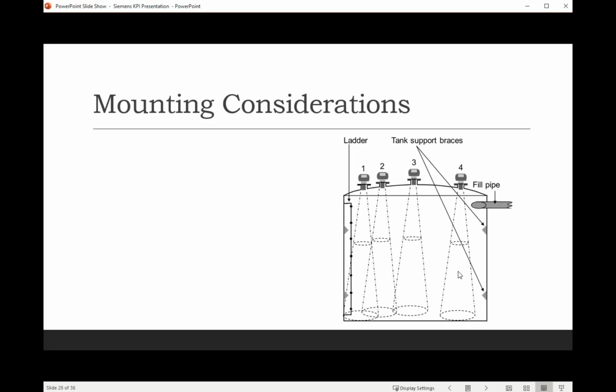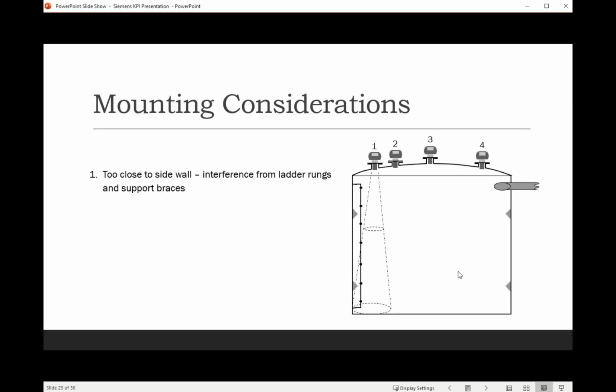So just for the transducer purposes, on this tank we have 4 different locations, and then in this tank you've got a ladder, you've got your fill pipe, you've got your tank supports. So obstructions are out there. So with mounting consideration number 1, say you're too close to the wall, you might catch on to the ladder. As your level decreases, you might have a false reading that is the ladder, and it might stick at a certain level, and that's going to cause problems over time.